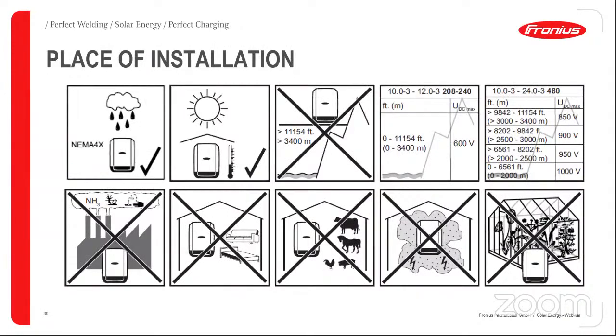Good, so all above inverters have an environmental protection of IP65 or NEMA 4X, which allows you to locate the inverter outside and is protected from heavy rains or big storms. It is also possible to locate our inverters in an altitude up to 3,000 meters in the Symo and 4,000 meters in the Primo inverter. Of course, please don't install the inverter in a bedroom because it can be a little bit noisy, similar to a fan operation. Also, please don't install the inverter in a farm. We may have some problems with animals. And be careful with very dusty places. It can block the fans inside the inverter. So these are only the recommendations, but basically we can locate our inverter in all the places.